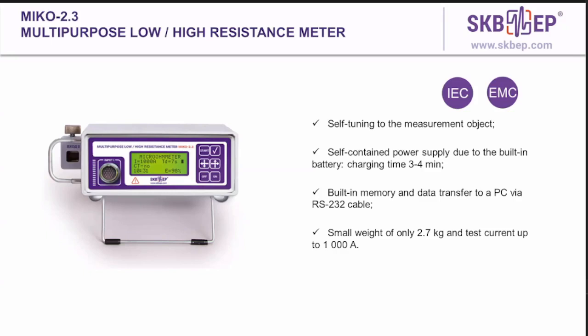It operates in 4 modes. Main mode is micro-ohmmeter. Then we have milliohmmeter, kiloohmmeter, and thermometer. Main features are that it has a small weight of only 2.7 kilogram and test current up to 1000 ampere in the micro-ohmmeter mode. It has the built-in battery with charging time 3 to 4 minutes.